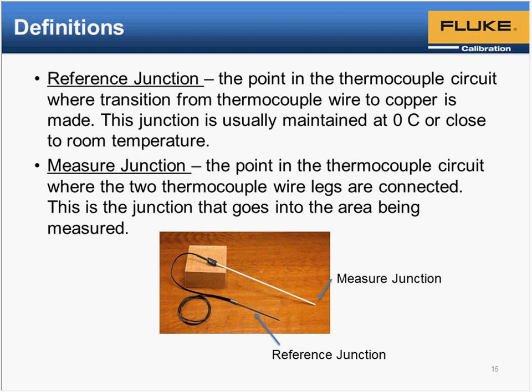If you want to take a look at that one: we would like to read the air duct temperature of a 4-inch diameter tube. Can I use 5 thermocouples, connect them in parallel, and calibrate these 5 thermocouples? Oh yeah, I see this a lot in several factories. It's one reason why thermocouples are popular. You can make a lot of them and do lots of interesting temperature uniformity tests with thermocouples. So this is a very common application where you take multiple thermocouples and bundle them together into a nice uniform heat source, and you check them and verify that they all match.